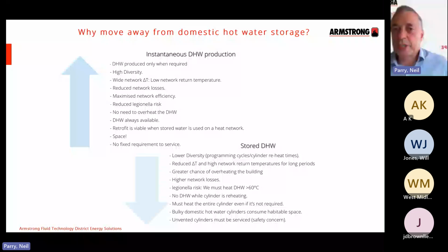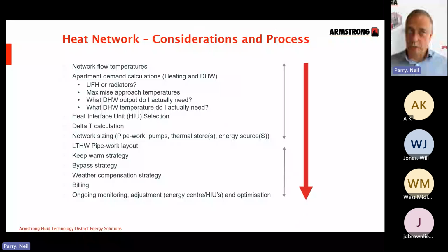So the process of calculating the heat network, or doing the calculations, the first thing to do is to work out what your network flow temperature needs to be. The reason that comes top of the list is it's normally dependent on your energy sources. So if you're going to do a solely heat pump led network, it may be that you need a flow temperature of 55 degrees, for instance. Obviously, you can use different refrigerants that can give you higher output temperatures, but it may be that your energy source is the dictator of your flow temperature. So once you have that, you'll note I haven't put the return temperature in there at that point, and there's a very good reason for that.